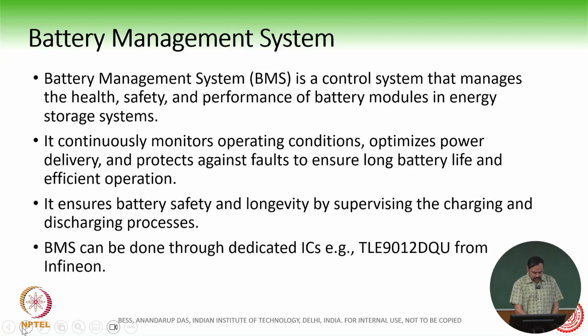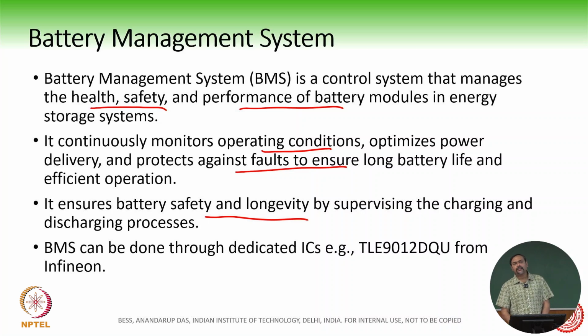A battery management system is an essential component for the battery energy storage system, because it manages the whole energy flow. Not only does it do charge and discharge of the battery, but it also controls the health. It is responsible for the safety and performance of the battery modules. It monitors the operating conditions, for example the temperature, and protects against faults to ensure a long battery life, safety, and longevity.